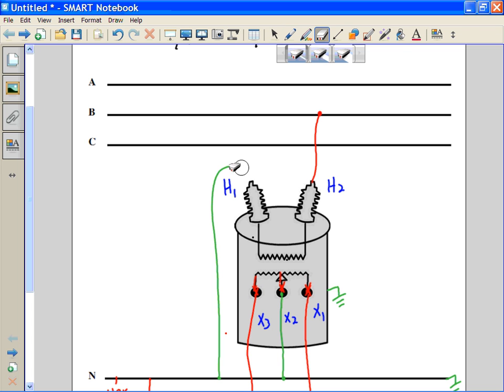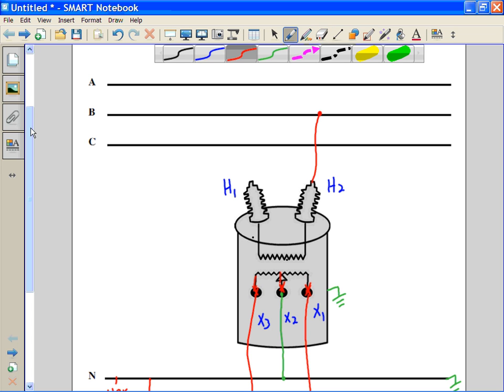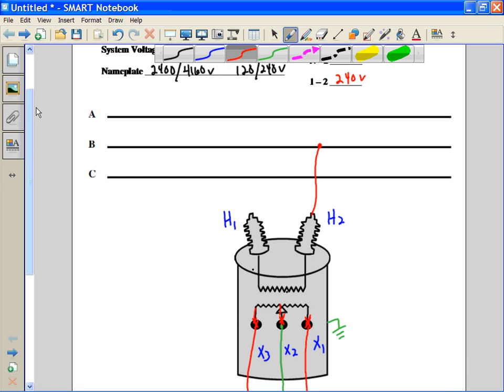So I'm going to erase the primary connection down to our neutral. And now, in order to get 2400 volts across the primary coil of this transformer, I have to connect to two different phase wires on the primary side. So I'm already connected to B and to H2. If I take and run a jumper from C phase down to H1, now I've created a delta connection on this single phase transformer.